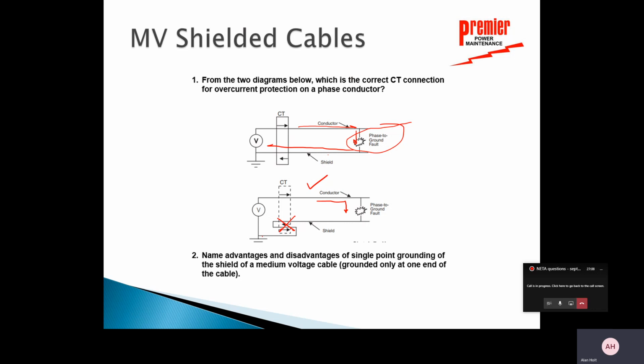But here's the huge one. During a phase to ground fault, the fault current will flow through that shield, and the cable can be damaged because of that fault current, when really it did not exceed the conductor capacity, but the shield is not able to carry that kind of current. So I could actually destroy the cable by having it grounded at both ends.